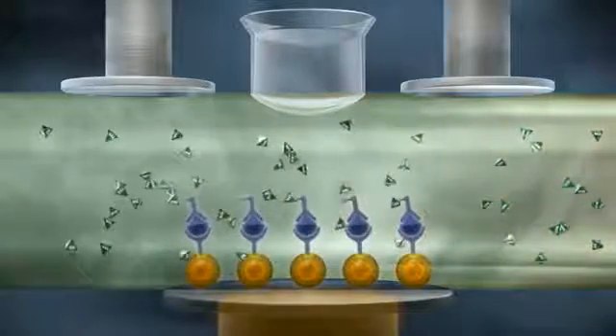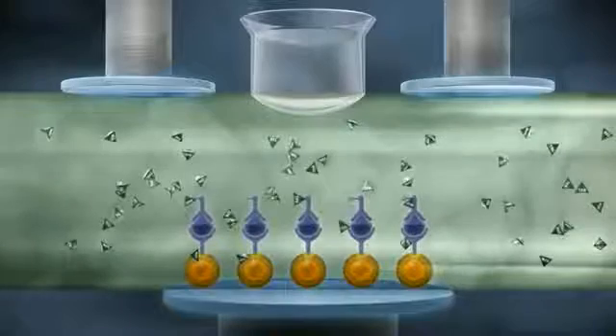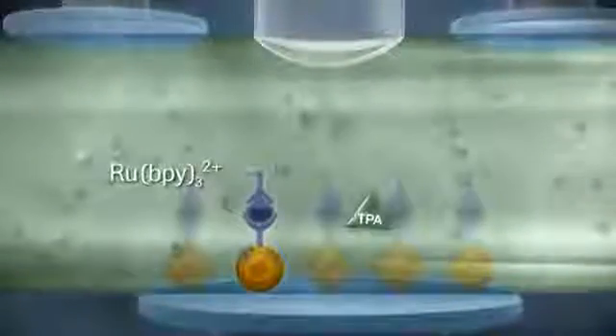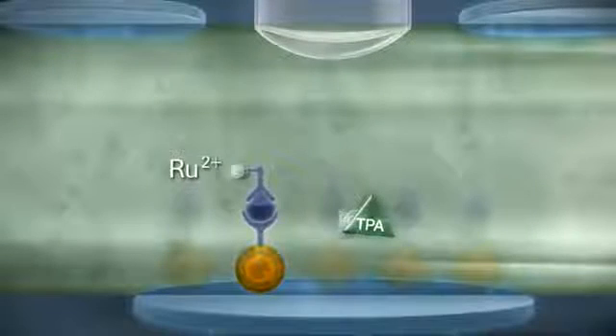ProCell solution is introduced in order to separate the bound immunoassay complexes from the free remaining particles and to provide TPA, which is essential for the ECL reaction.